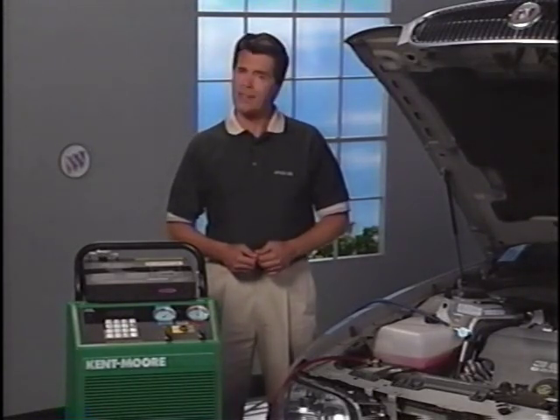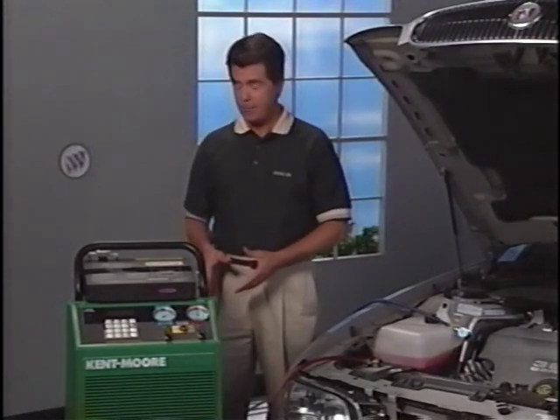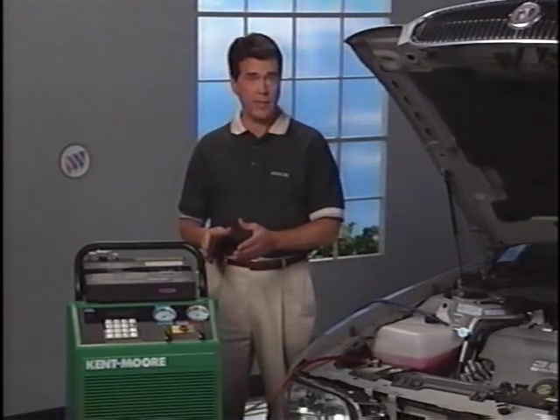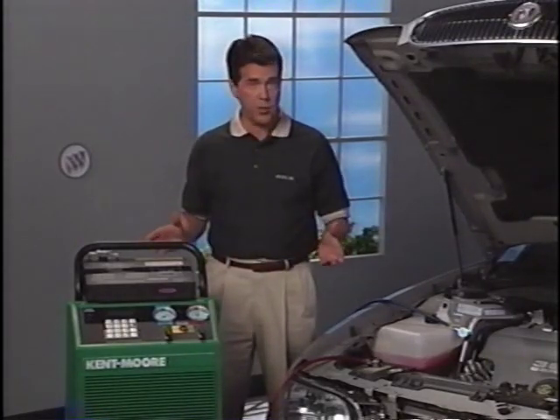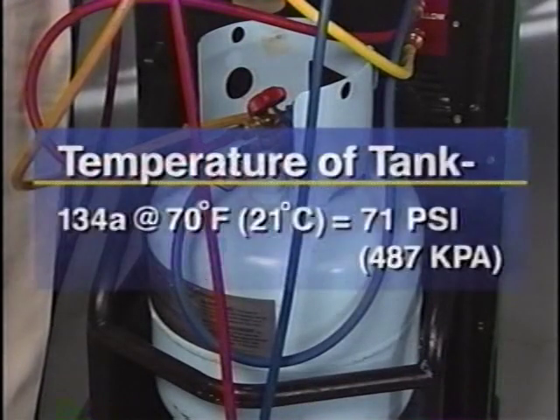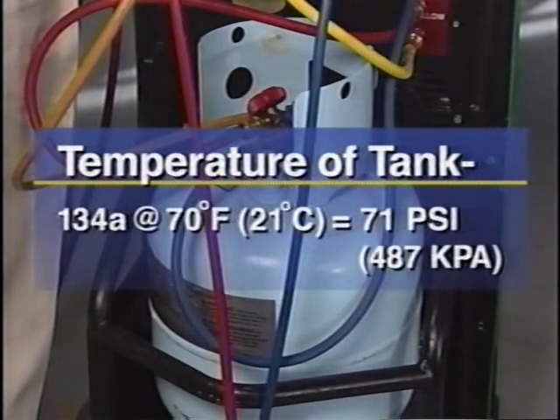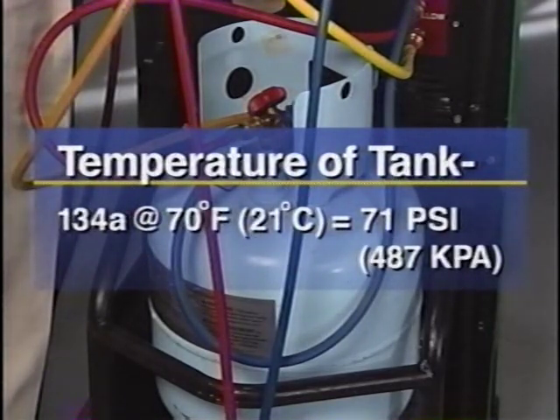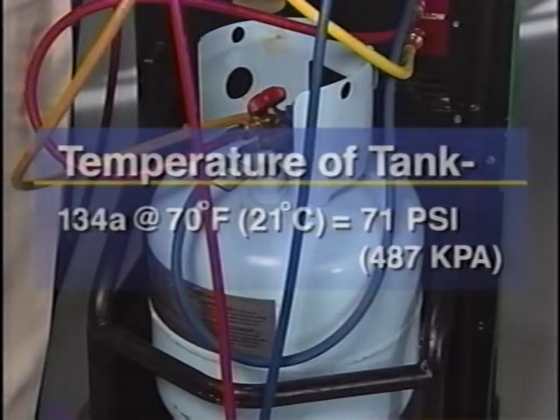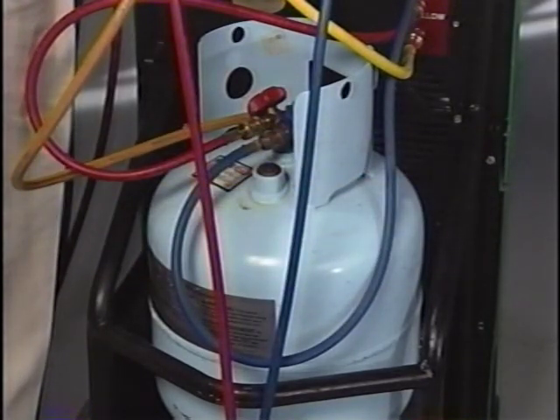You can gauge pretty closely how much air is in the tank by checking the pressure of the refrigerant tank against the ambient temperature where the tank has been stored. Let's say, for instance, the tank has been sitting in the shop overnight at a temperature of 70 degrees Fahrenheit. The pressure of 134A at 70 degrees should be 71 psi. So if you get a reading of, say, 90 psi, then you know you have about 20 pounds of air in the tank.